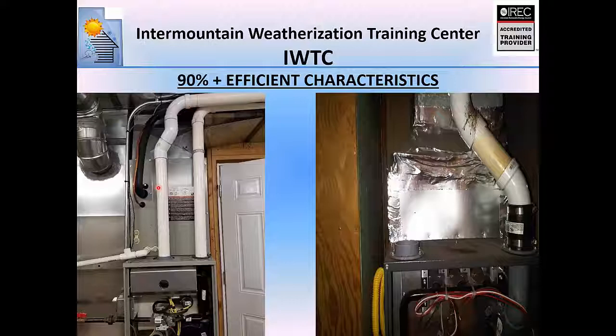That's called direct vented. And it's got a sealed combustion chamber down here. There's no way that you can cause this thing to backdraft into the house. If it were to backdraft for some crazy reason, the flue gases are going to come down here through the inducer, through all the heat exchangers, sealed combustion chamber, and back out here. I have yet in my lifetime to see one of these things backdraft, okay? Because they're sealed combustion and because they're vented properly in what's called the direct vent configuration, two pipes to the outside.